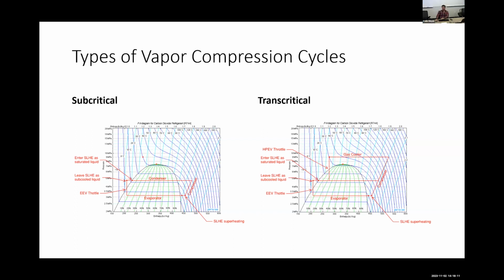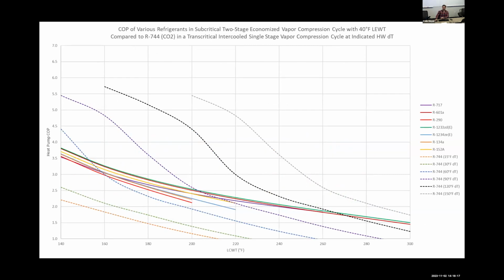So in the gas cooler, there's a large temperature change because we're not a saturated gas to a saturated liquid. Because of the temperature change, there's a large impact on how efficient the process is from entering temperature to leaving temperature. And that's what this chart shows. And that's why you're seeing CO2 used in domestic hot water heating systems that have high range. There's possibilities of COPs in the range of 5.